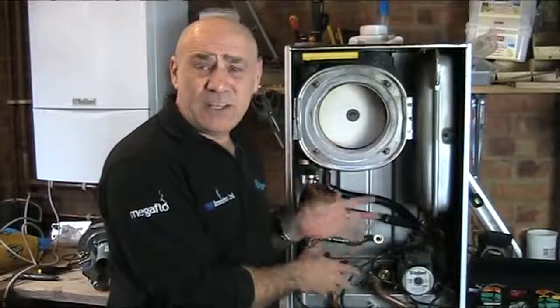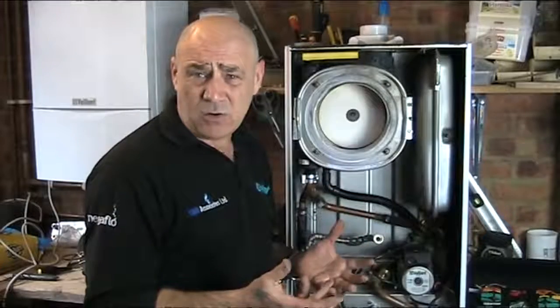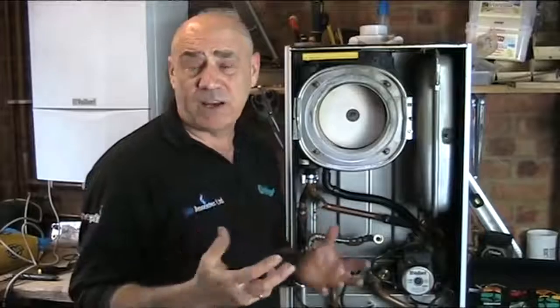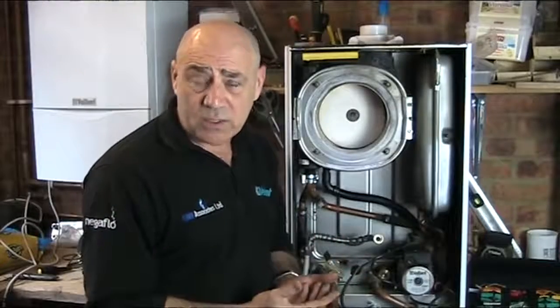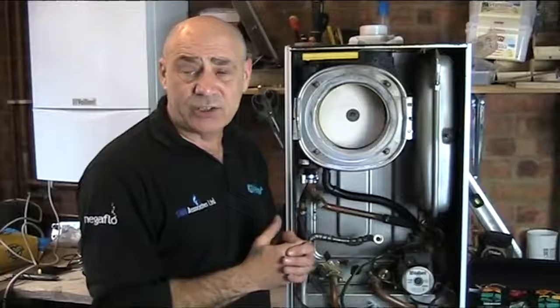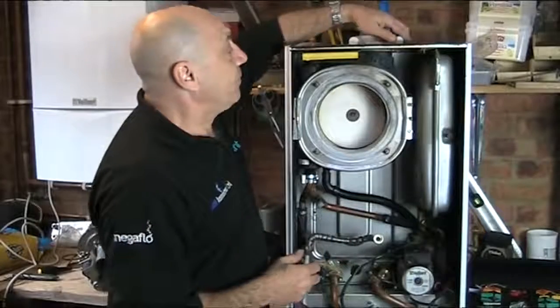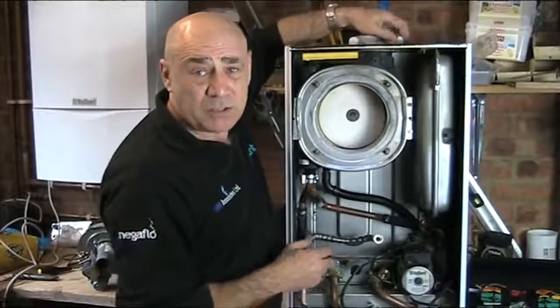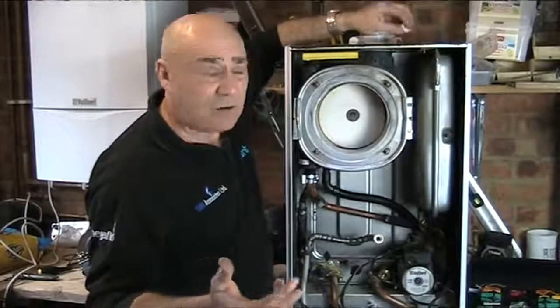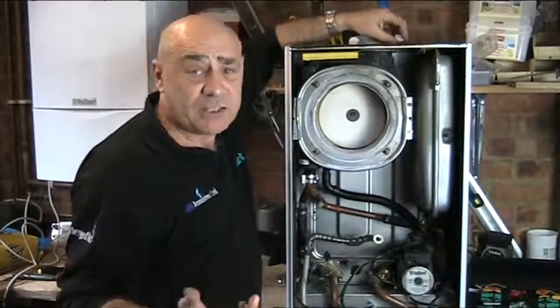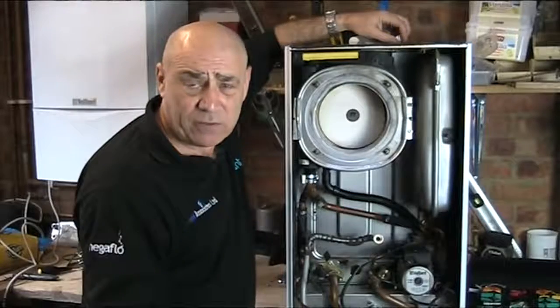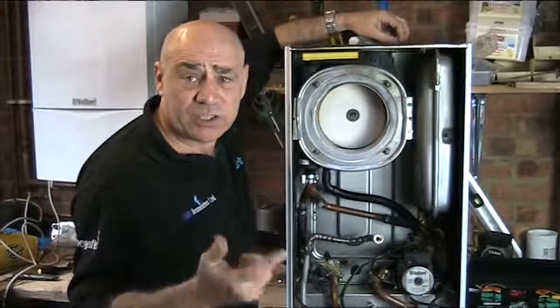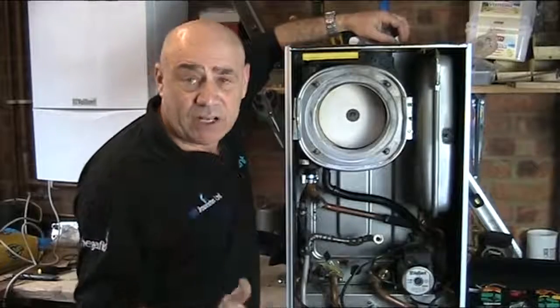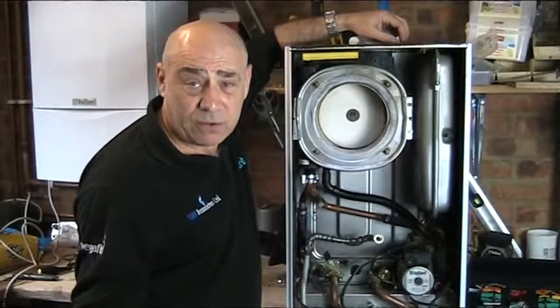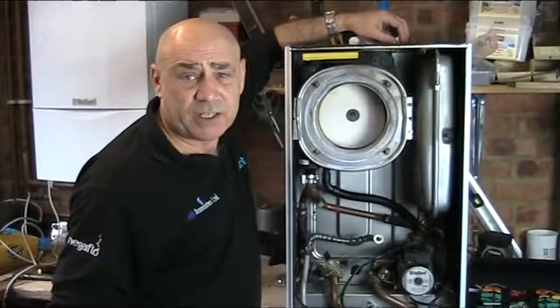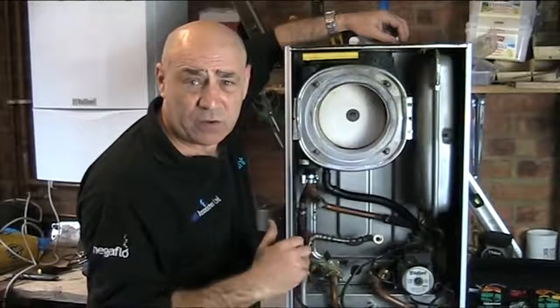Once the boiler's gone through the P0 program, we can then turn the boiler back on and run the system. So that's when we'll go around and check your controls to make sure everything's switching in and switching out as it should. We will then take a sample from the top of the flue here using a flue gas analyzer, and we will read off all the combustion readings again, which will go onto your service record. So we'll have the CO2, the CO, the oxygen and the ratio readings, as well as the gross flue temperatures. All the combustion readings will be listed on your service record.